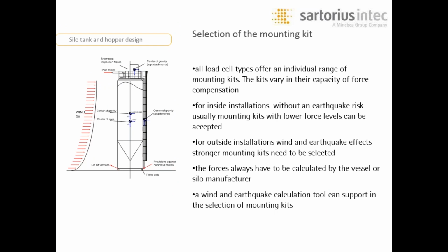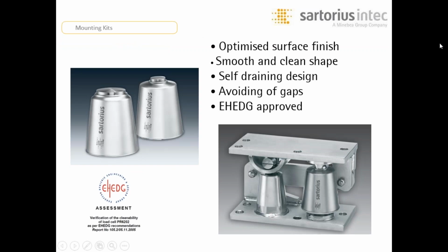Inside installation is where you have an earthquake risk. That's where you have to determine if you need a seismic mount or if you just need some heavier constraining within the load cell mount itself. Outside, you need to take into consideration the center of gravity, attached devices, and also wind. Wind can be a big factor, and there are other maps that show where we have a higher propensity of wind in the U.S. That needs to be taken into consideration when deciding which mounts to go with.